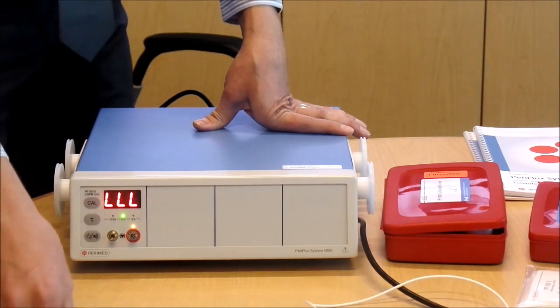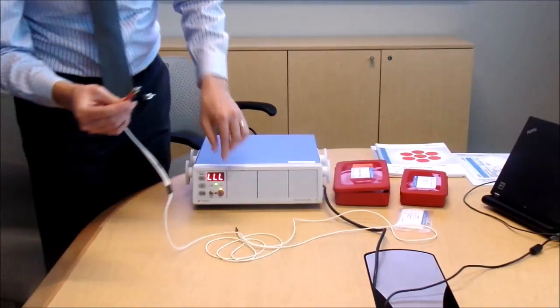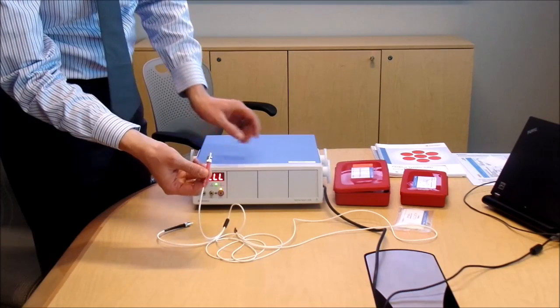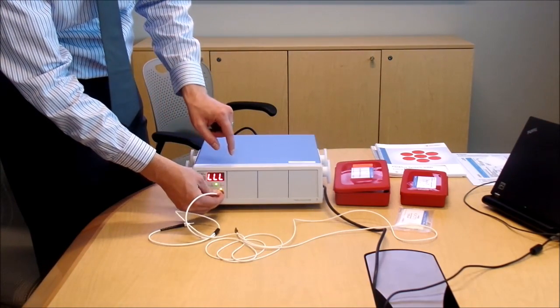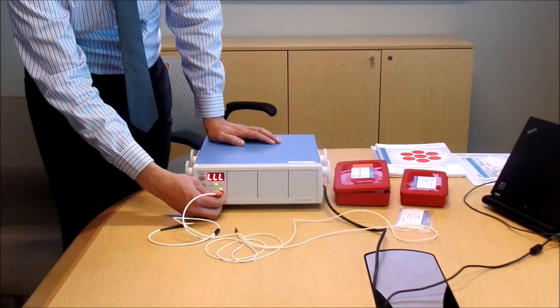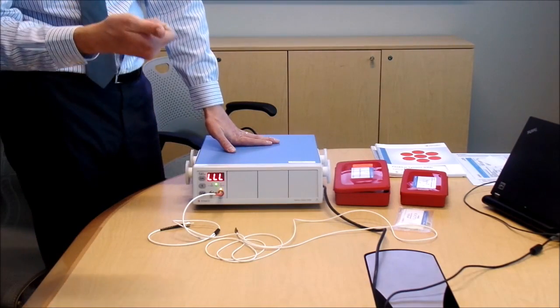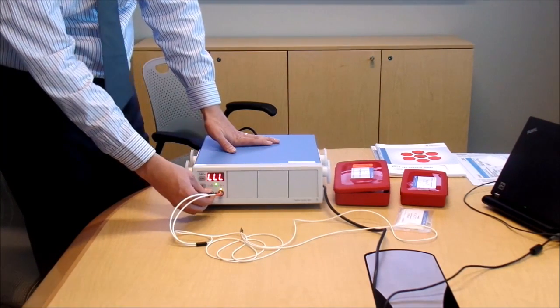So the probe itself, you have two connectors. You have the red, which is for the transmitting fiber, and the black, which is the receiving side. The connectors for the probe have this little color key right there, the red key, so you know where these connectors go. To insert the probe properly in the machine, for the red side, the transmitting side, you have to rotate this connector around a little bit until you feel it slide all the way into the receptor, and then you push the outer casing here, I hope this shows up on the video, twist it sideways and it will lock on these pins here on the receptor sides. This, I think, is called a bayonet type fitting. The receiving side, a little bit easier, plug it straight in, and again, that bayonet type of connection.